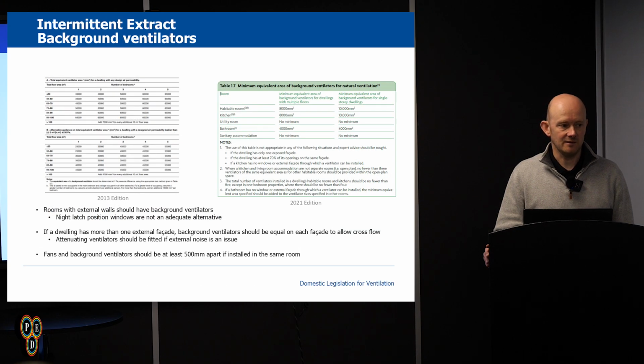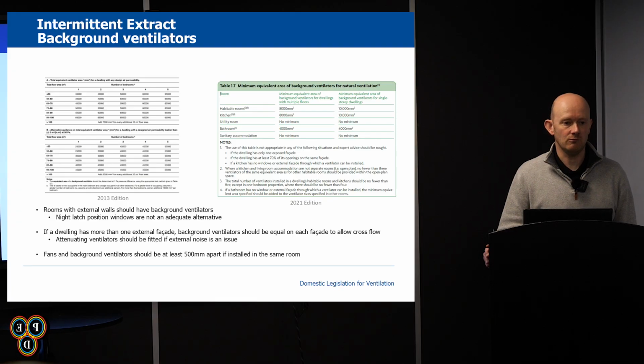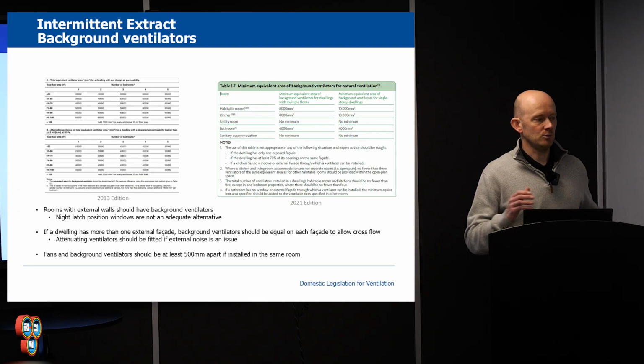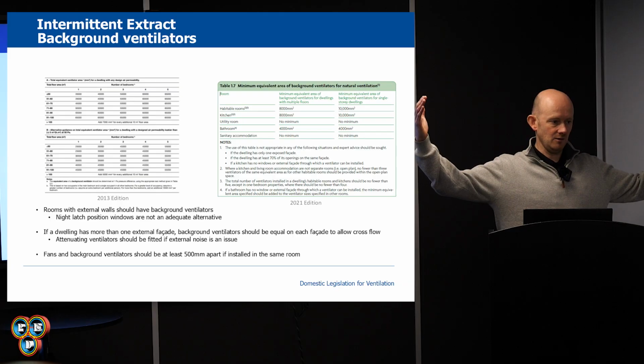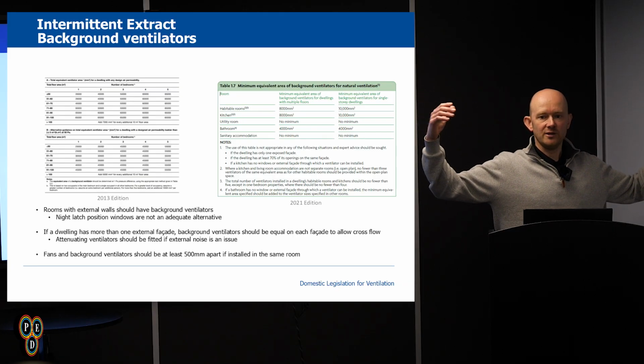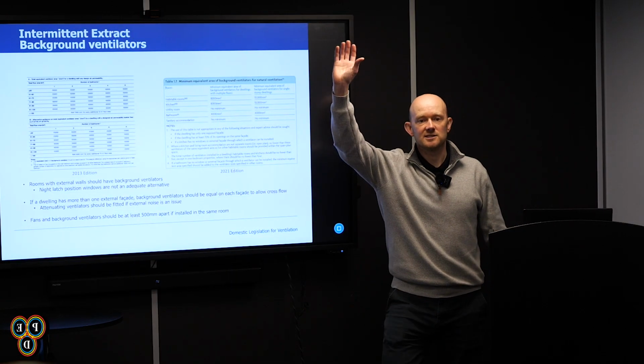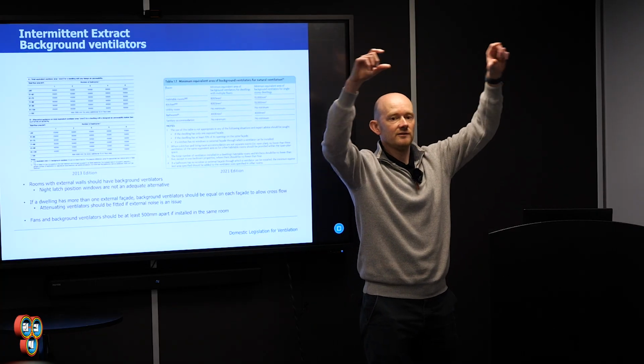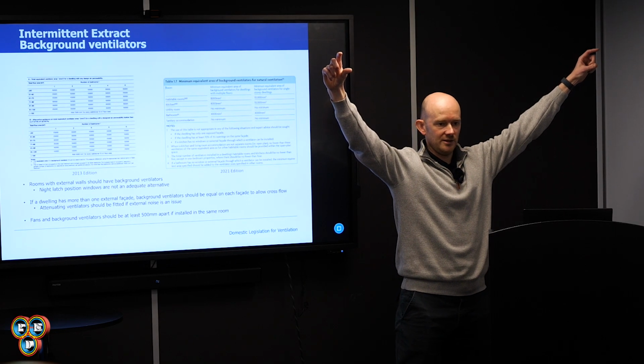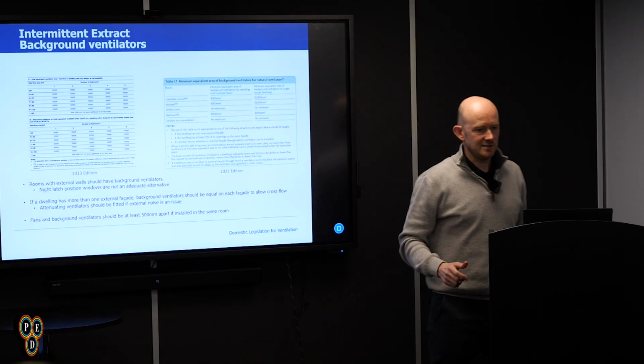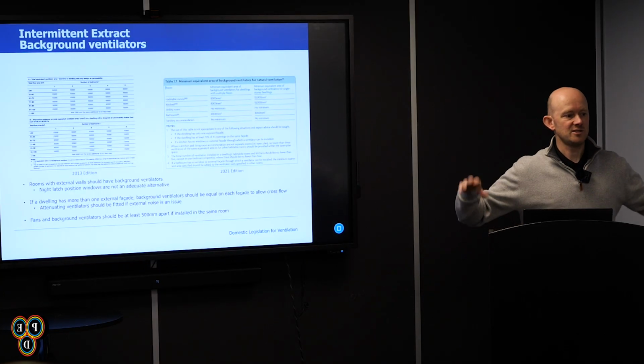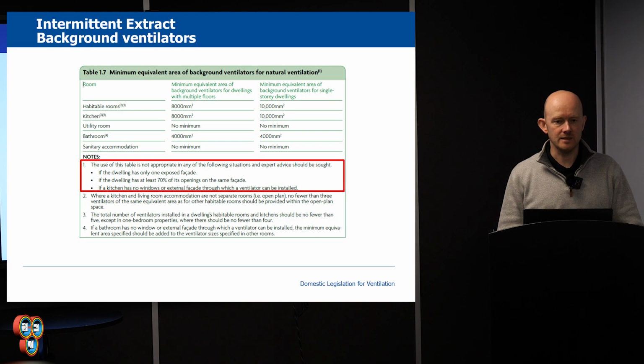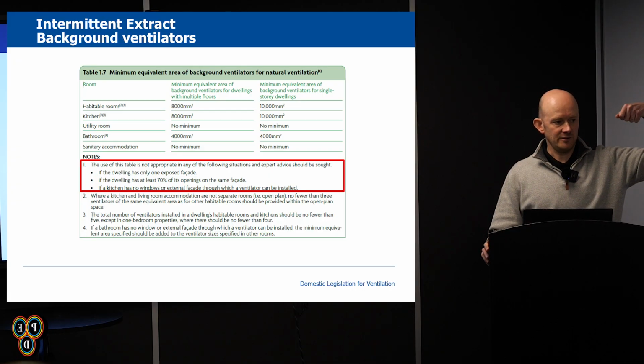To attenuate a fan that backs onto a railway line or an airport runway, you wouldn't be able to do it straight through a wall because an attenuator is a metre long. So that would only work if you were able to mount a fan in the middle of the ceiling and have a duct run, and then be able to fit an attenuator in between the joists before you get out. So it's not just as easy as just attenuating a fan. What we're finding is any build happening near a railway line or an airport is just MVHR. They're stopping people having trickle vents and stuff to stop any noise coming in.